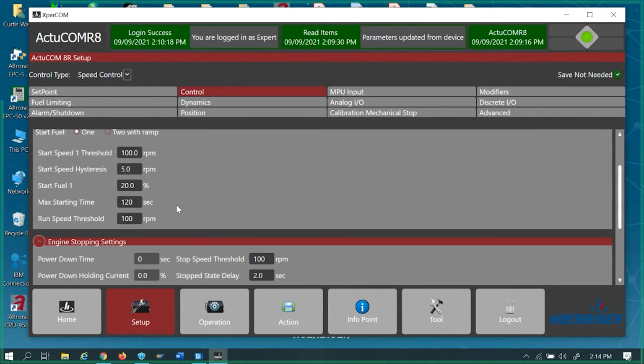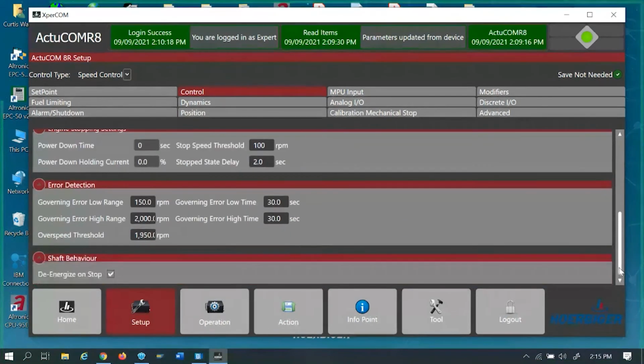Max starting time, just like it says, if it doesn't start in 120 seconds, shut it off. Run speed threshold, when the governor goes into run, when it says I'm running or self-sustaining, that's the RPM it typically does that with. Engine stopping settings, you have power down times in seconds. Your stop speed threshold, if it gets within 100 RPMs difference, we can stop it. Power down current, hold current, which I never mess with any of that.